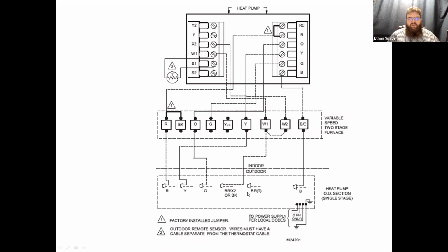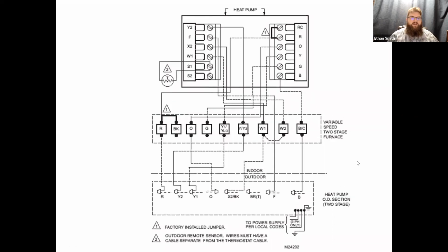There is a brown wire in some of the older units. That brown wire is typically unused in modern controls. That brown wire was there to signal an error light on the thermostat. Almost nobody has that anymore, so we don't use it. And I believe brown's actually been abandoned in all of the non-communicating units. In the communicating units, brown is now data, typically. So there would be a multi-stage outdoor unit where we've got Y1 and Y2. And then, of course, O, common, defrost, our black wire going into our W terminals for defrost, things like that. Lots of different ways to do it.